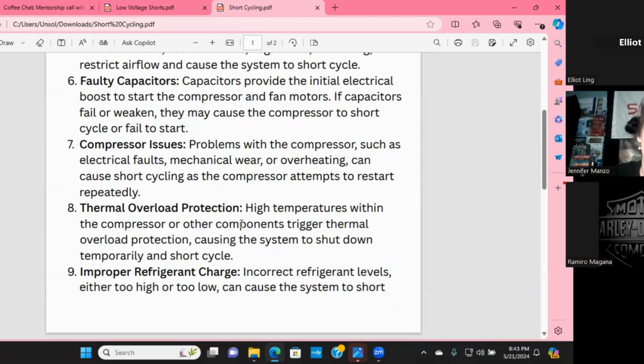And that is when we run into this problem. Thermal overload protection, another problem. That's when we have something raising the head pressure, whether it be dirty or low charge or many things. Something is causing the compressor to protect itself and go into thermal overload lockout. We call it thermal lockout.